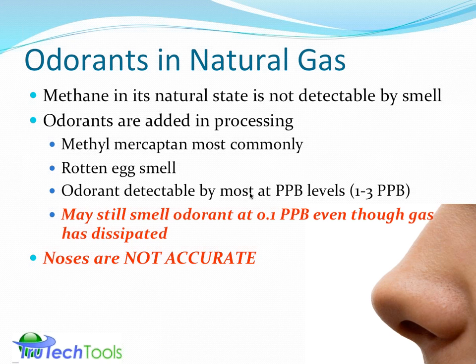So from all of this, even though it's done as a public service or as a courtesy, noses are not accurate detectors. Some people cannot detect even the methyl mercaptan smell at the same level. So there's a very wide-ranging response by the human body to the odorant. They're not meant as an accurate indicator. And also there's a concept called olfactory fatigue, which basically means you smell something long enough and it doesn't smell anymore. It doesn't react anymore. So this all sums up to odorants are not to be relied upon as a measurement.